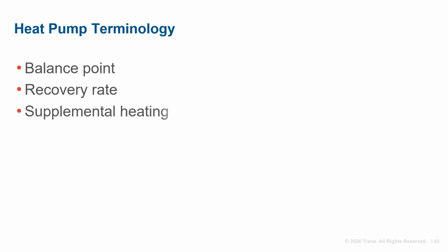Many heat pump controllers use logic to monitor the space temperature and manage the recovery rate. This logic may be performed in a conventional thermostat or by the equipment's microprocessor. As ambient conditions change, the controller will monitor the space temperature and recovery time. If the mechanical heating cannot maintain the space temperature, the logic will automatically enable supplemental heating.